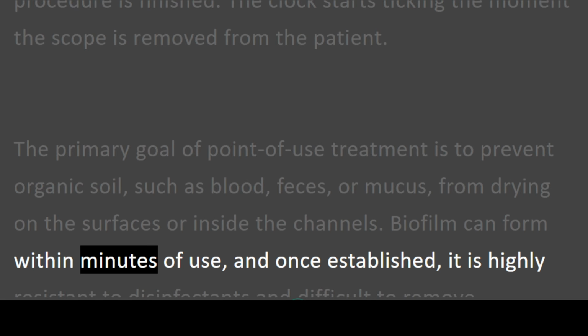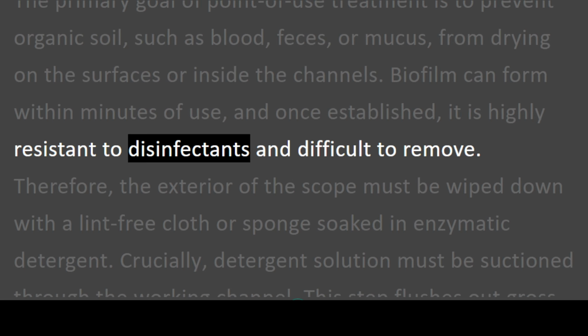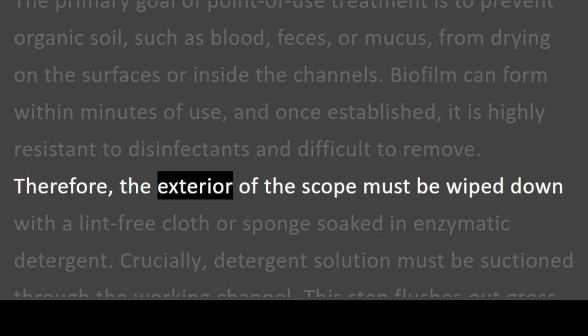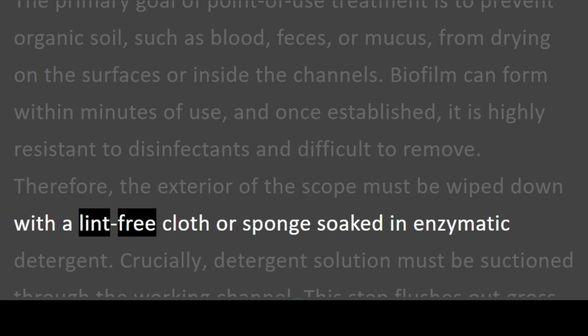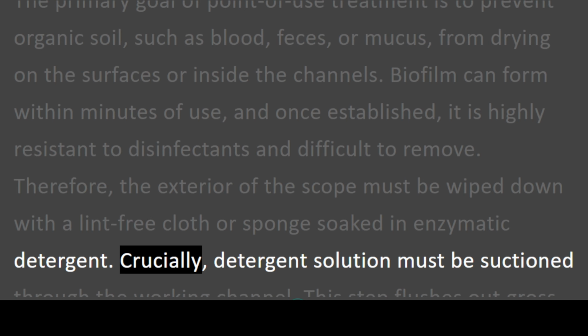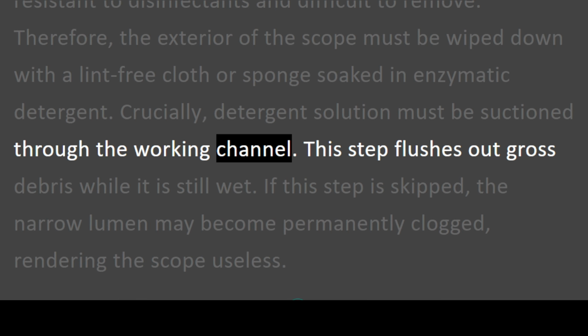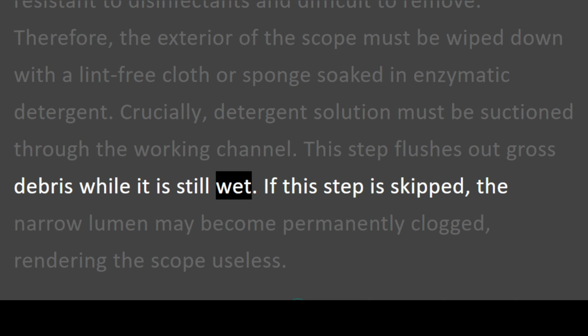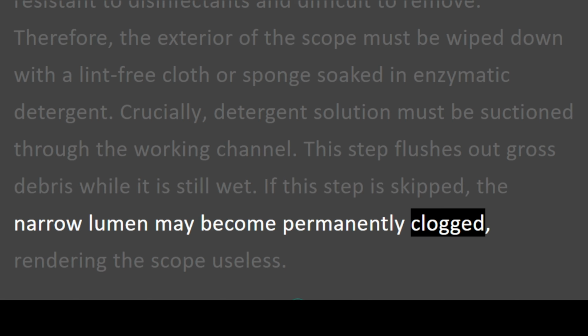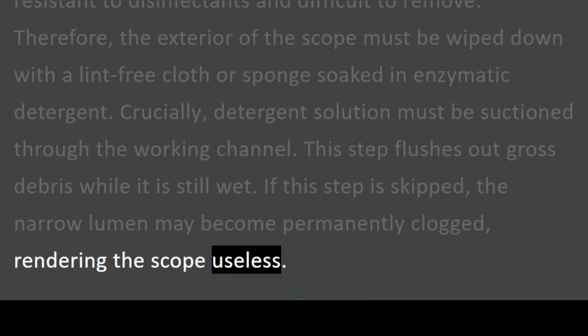Biofilm can form within minutes of use, and once established, it is highly resistant to disinfectants and difficult to remove. Therefore, the exterior of the scope must be wiped down with a lint-free cloth or sponge soaked in enzymatic detergent. Crucially, detergent solution must be suctioned through the working channel. This step flushes out gross debris while it is still wet. If this step is skipped, the narrow lumen may become permanently clogged, rendering the scope useless.